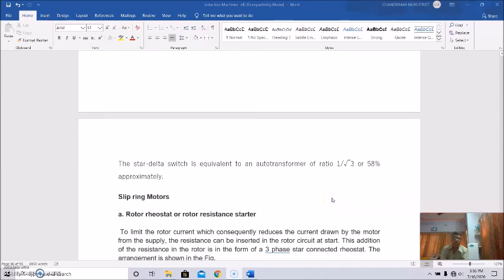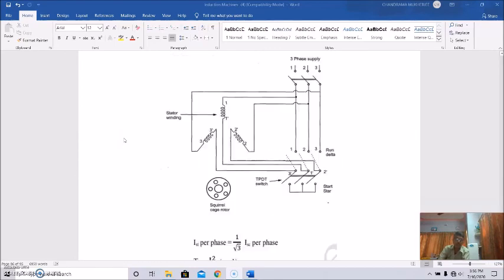So the star delta switch is equivalent to an auto transformer of ratio 1 by root 3, or 58% approximately. So that's all about the different starters for the squirrel cage induction motor.